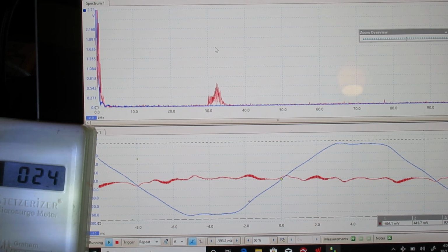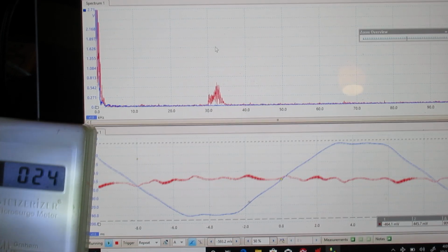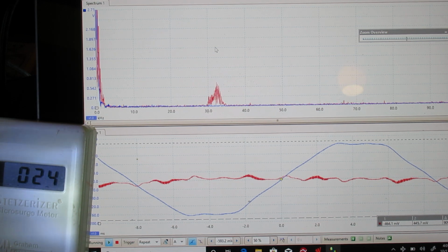So it's possible that you could put one of these in for 100 amp service, which they have two of here. It could be about $15,000 twice. That's $30,000 and another $10,000 worth of electrical hookup. So you'd be looking at about perhaps $30,000 to $40,000 to use the very most effective filters. There is another solution, and that is simply to remove the problem, and that would be the pool pump. And the pool pump is the culprit.